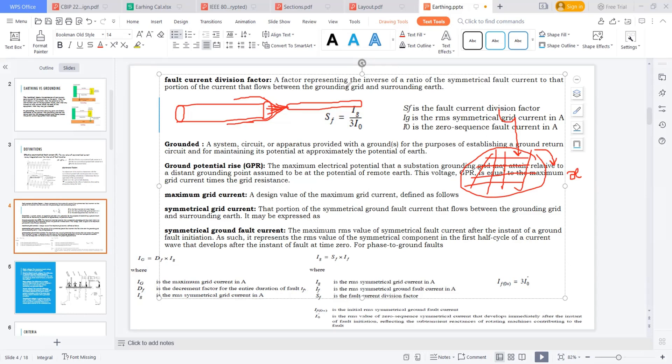A factor representing the inverse of the ratio of the symmetrical fault current to the portion of current that flows between the grounding grid and the surrounding earth. Suppose IG is the symmetrical grid current. I have a grid, so some current will flow through this grid and some current will flow into the system.